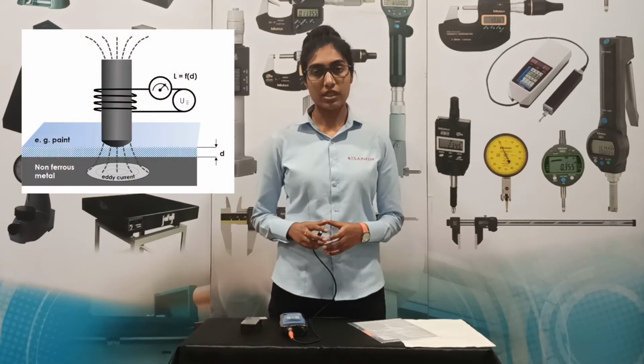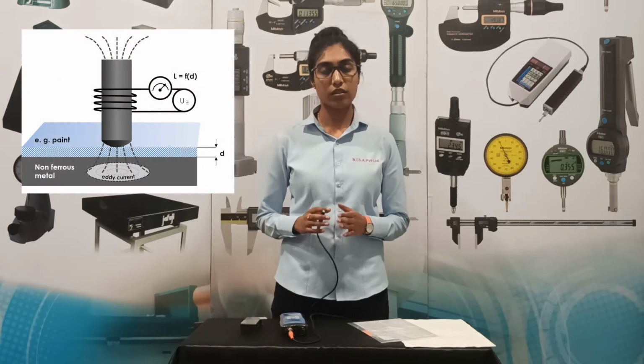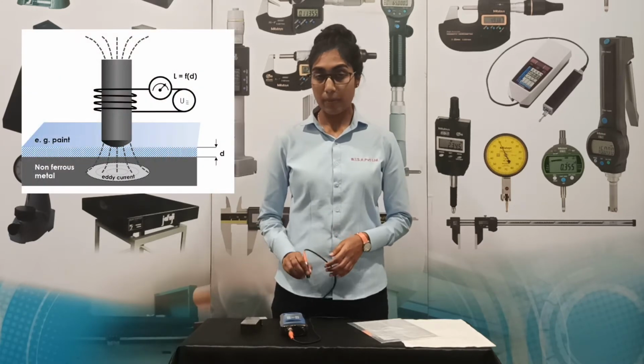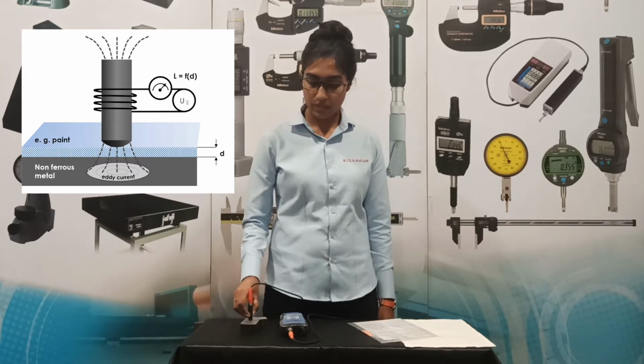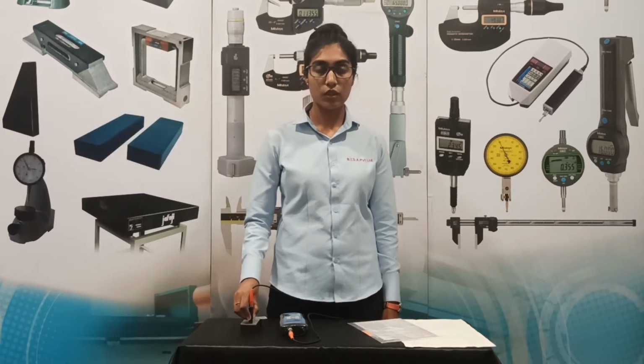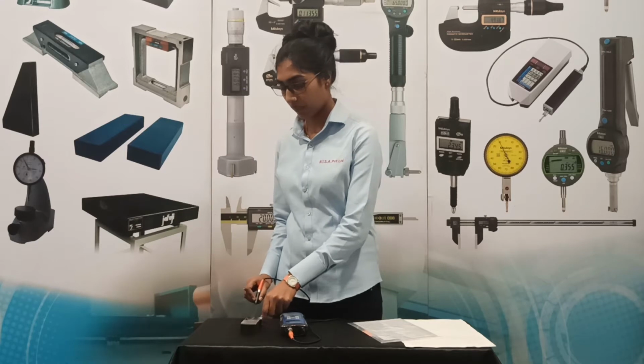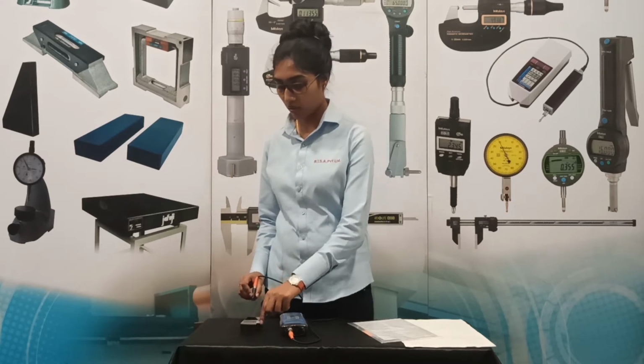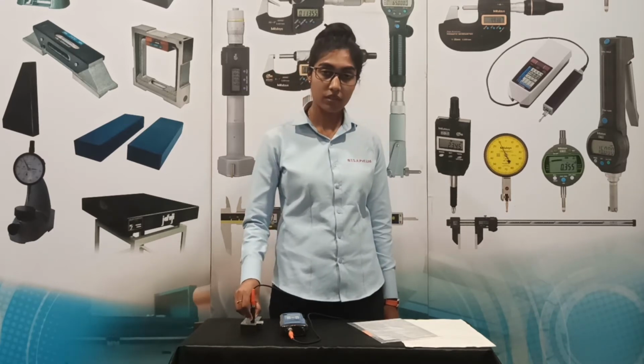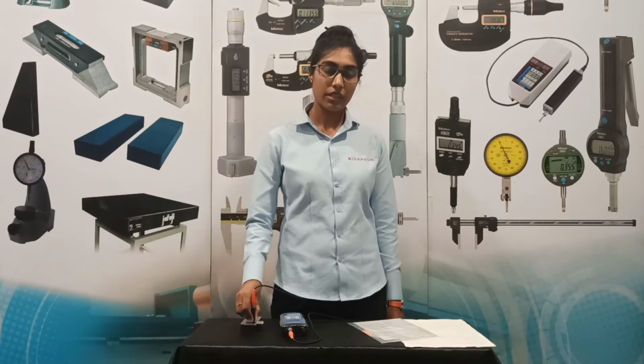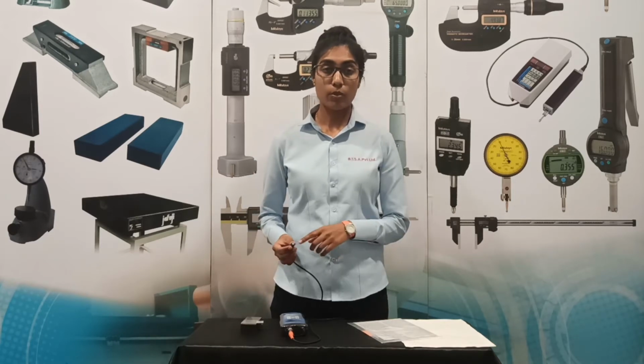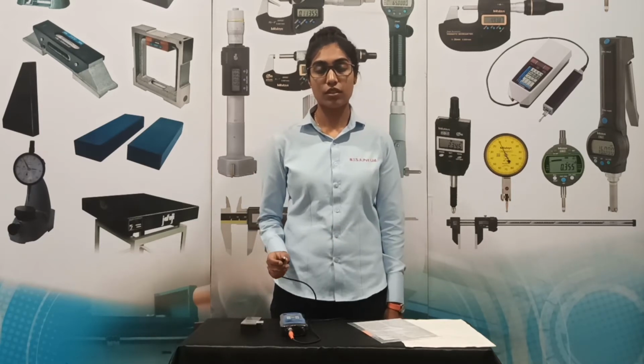In the eddy current principle, the electric current flows in a circular loop within its conductor. By placing the sensor on the non-ferrous substrate, the electric loop gets generated. By placing a non-conductor on the surface, the electrical loops are disturbed. Hence, the distance between the probe and the substrate gives the thickness of the coat.